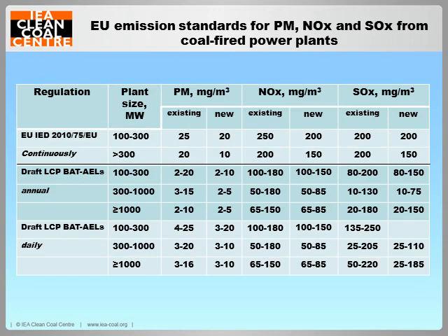The policymakers in the EU and member states have to fully comply with BREFs by setting emission limit values, ELVs, based on BAT associated emission levels. The emission standards are changing frequently and each time they change, they become stricter. The standards in BREFs are scheduled to be revised every eight years. The current LCP BREF is long overdue for review. A draft was produced last year, and the suggested BAT AELs are much stricter than the current values. The new BAT AELs have raised concerns from the power sector due to the economic impact of meeting the new limits.